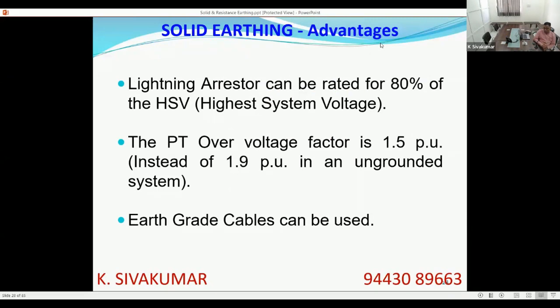Similarly, if you see the PT standard, IEC 61869 or IS 16227 part 3, there is a factor called overvoltage factor for voltage transformers. In an ungrounded system, the overvoltage factor is 1.9 for 8 hours, whereas here 1.5 for 30 seconds is more than sufficient. The PT standard says that in a solidly grounded system, it is 1.5 times for 30 seconds. Why? Because since the current can be detected and the fault can be isolated, a duration of 30 seconds is more than sufficient. So when you reduce the voltage factor, the VT size and the cost reduce.